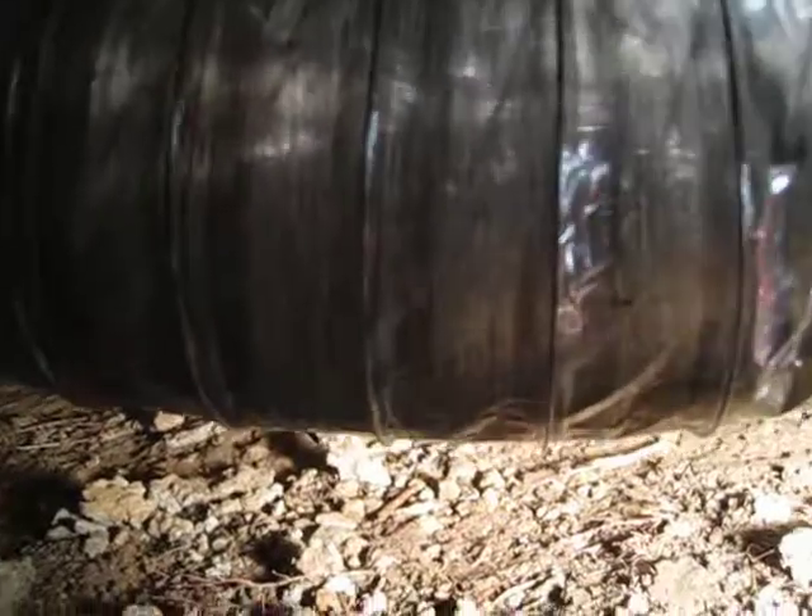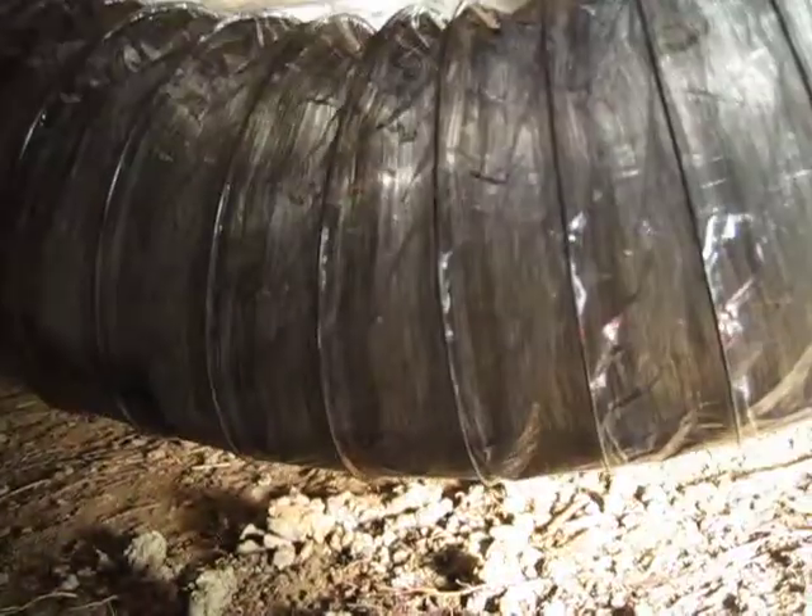However, what was misdiagnosed was the fact that there is water — standing water — on the inside of the duct as well. How long it's been there, how it got there, we have no idea at all, but the duct itself is sagging like crazy.